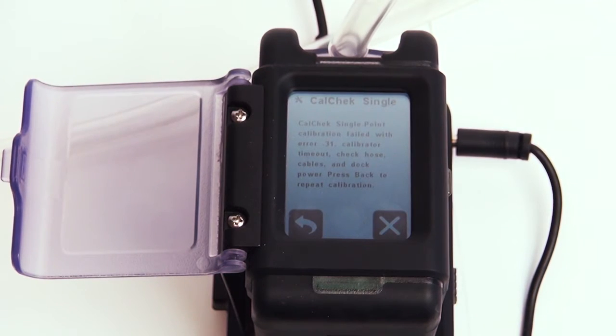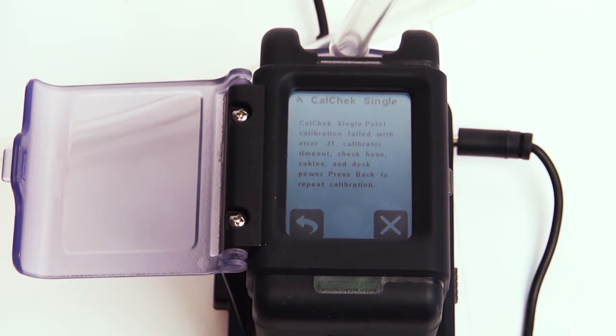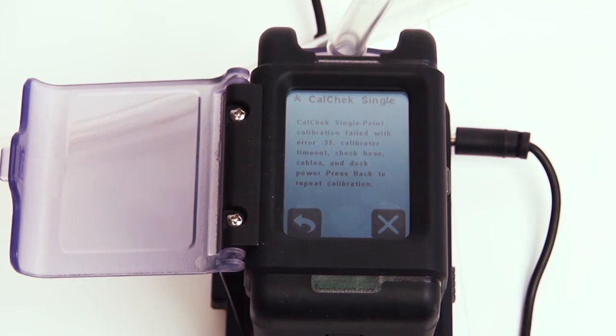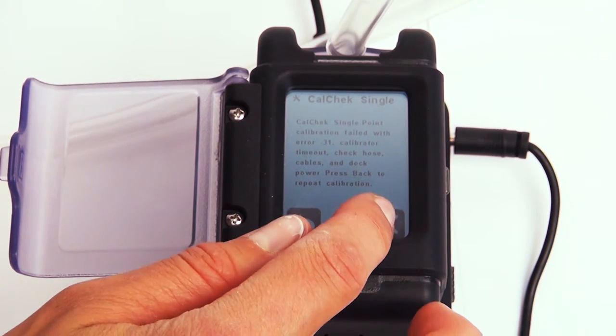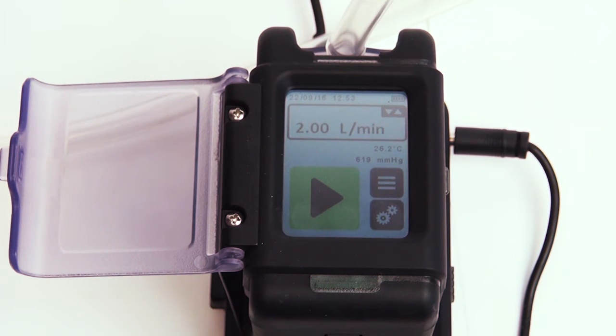If your calibration fails, the CalChek Single screen will read, CalChek Single Point Calibration failed. Touch the back button to repeat the calibration, or touch X to exit the calibration and return to the home screen.